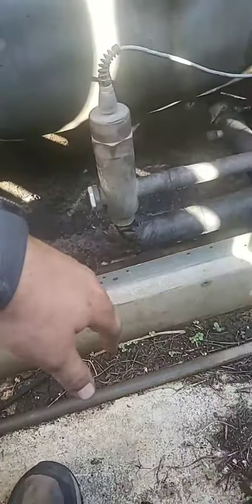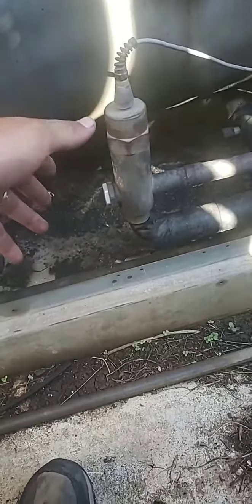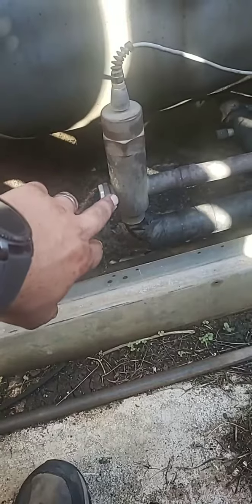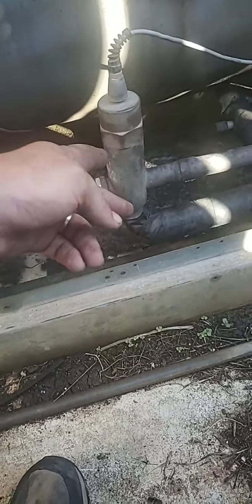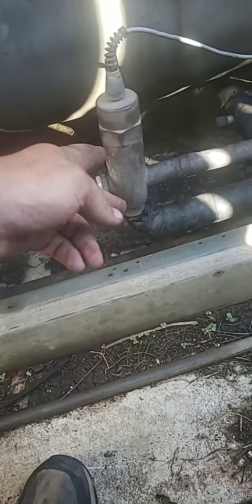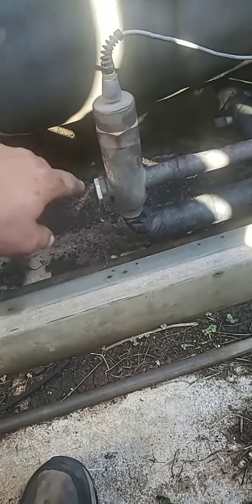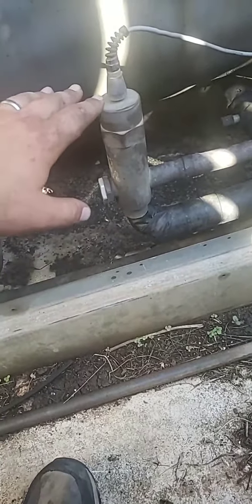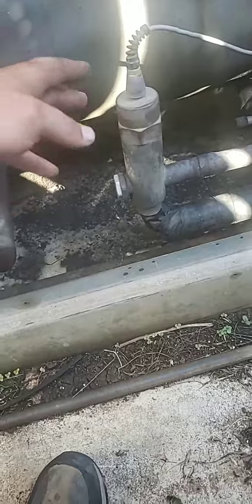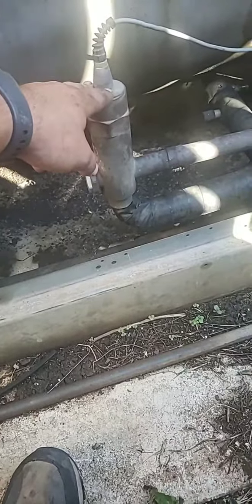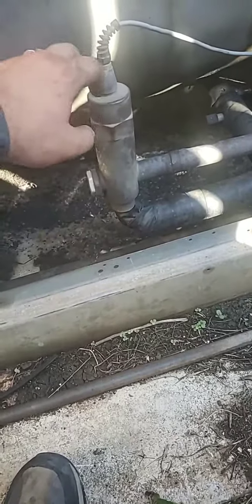Well, that was not happening on circuit B. So then at that point, it's either the valve itself or it's the board. What I did was I switched the A and B EXV plugs on the control board and redid the test. And sure enough, same thing happens. Circuit A's EXV calibrated, no problem.